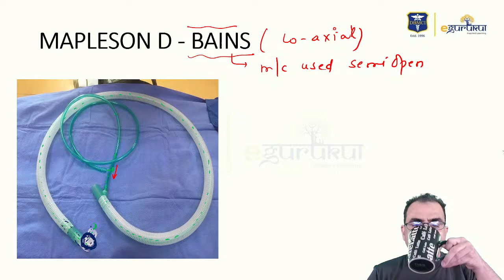Fresh gas flow recommendations for the Bain circuit. If you are using it for controlled ventilation, then the fresh gas flow requirement will be 1.5 to 2 times they say, but on average you can remember 1.6 times the minute volume. If you use it for spontaneous ventilation, then the fresh gas flow requirement is high, that is 2.5 times the minute volume. So obviously, we always prefer a circuit which uses less gas, and you can clearly see that the Bain uses less gas during controlled ventilation, making it the circuit of choice for controlled ventilation. And of course, avoid it for spontaneous ventilation because the fresh gas flow is very high.